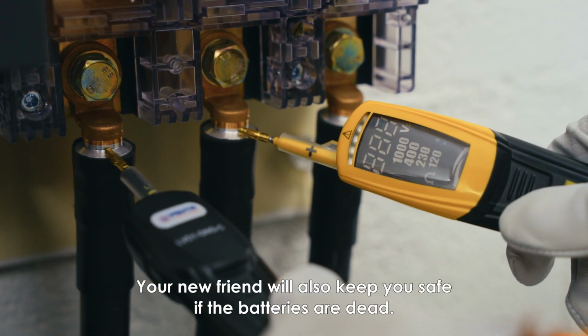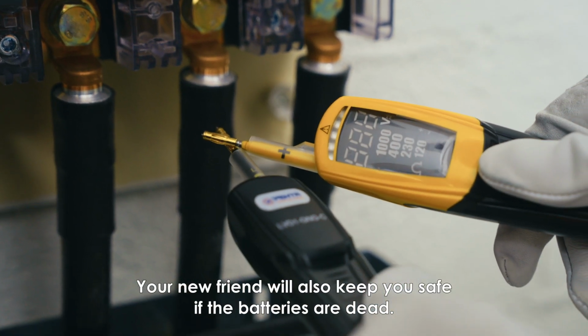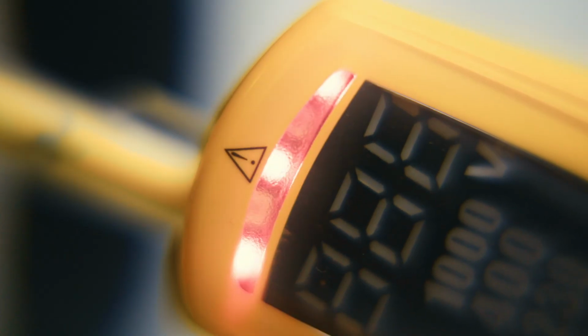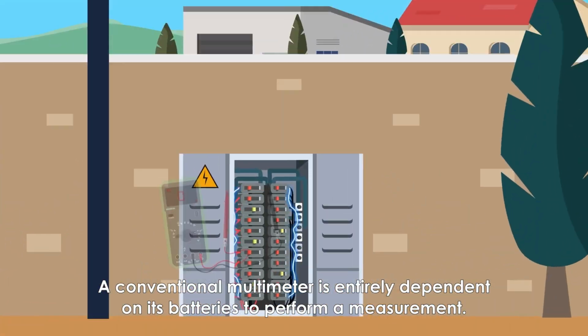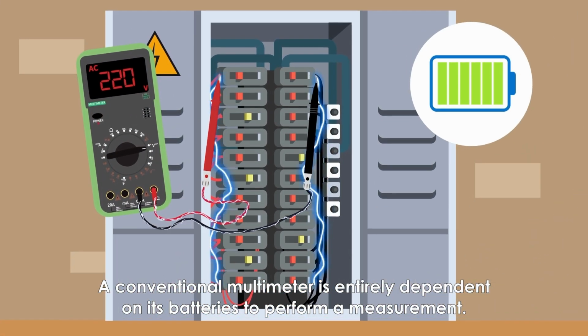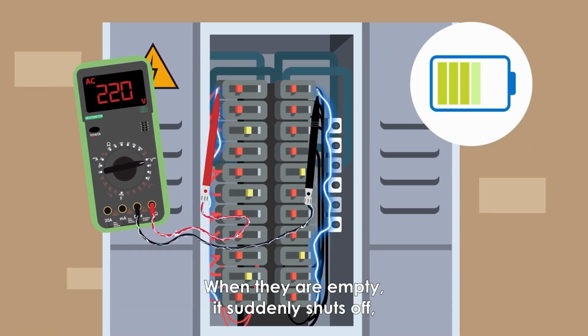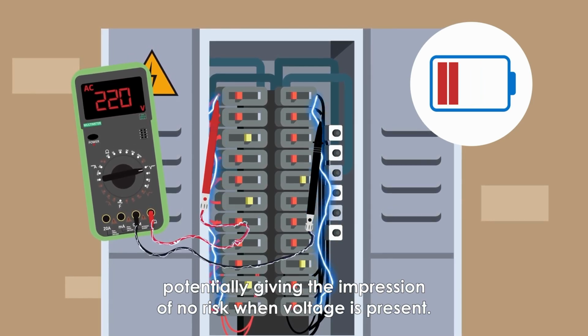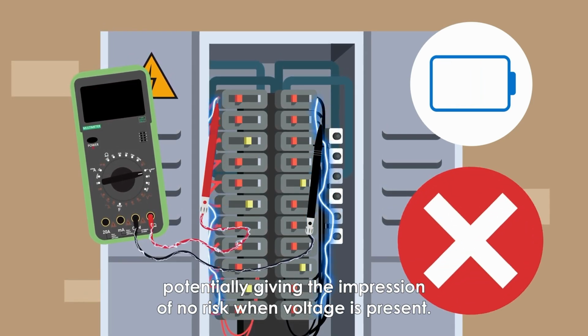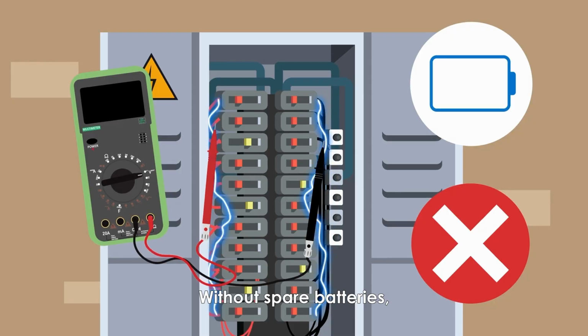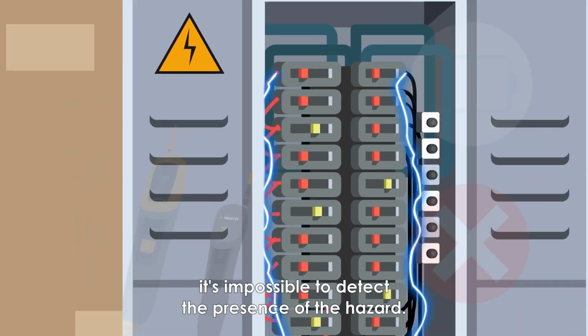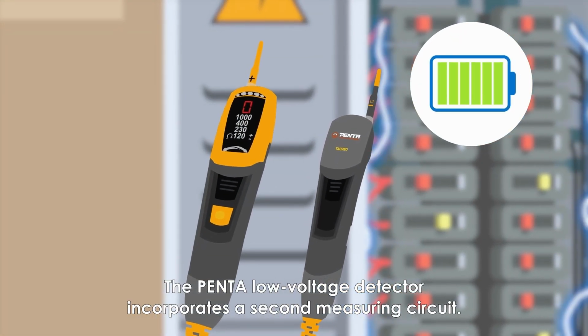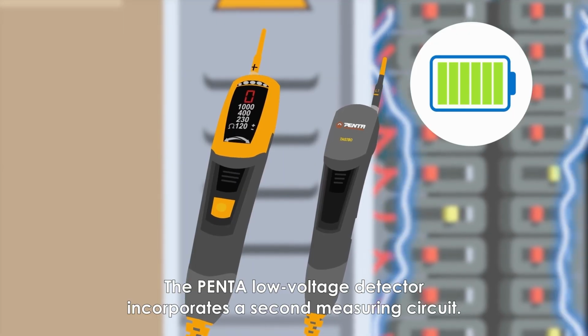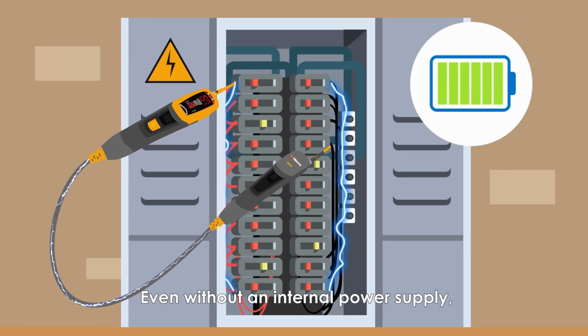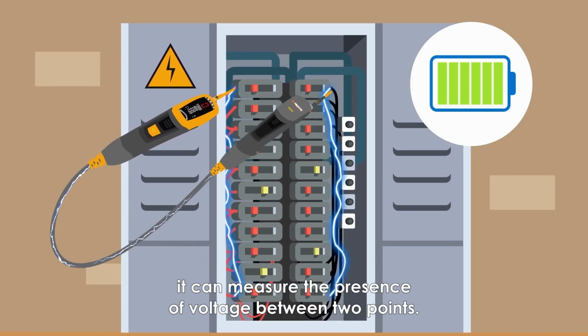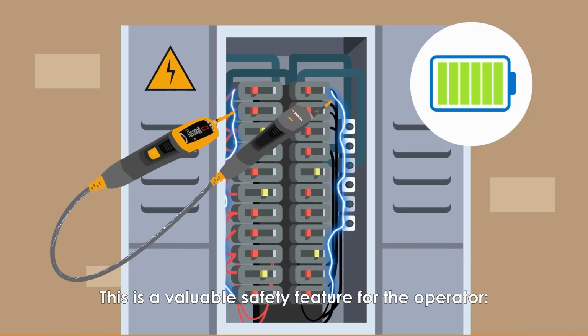Your new friend will also keep you safe if the batteries are dead. A conventional multimeter is entirely dependent on its batteries to perform a measurement. When they are empty, it suddenly shuts off, potentially giving the impression of no risk when voltage is present. Without spare batteries, it's impossible to detect the presence of the hazard. The Penta low voltage detector incorporates a second measuring circuit. Even without an internal power supply, it can measure the presence of voltage between 2 points. This is a valuable safety feature for the operator.